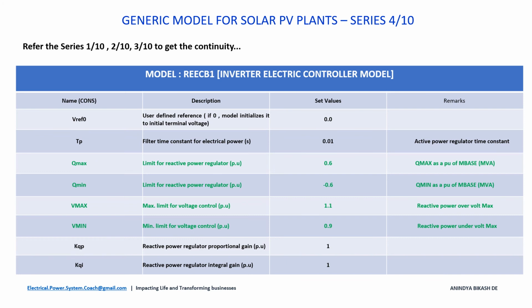Like in LVRT mode, it starts operating below 0.9. So 0.9 to 1.1, this is the continuous range you can say. And so below 0.9, it will go into LVRT mode, and above 1.1, it will go into HVRT mode. And there are various time instances, means from 1.1 to 1.2 it may withstand for certain seconds, then 1.2 to 1.3 it may withstand for certain lesser seconds. So likewise, this is the Vmax and Vmin. This is the nominal, and minimum and maximum value of the voltage during which the inverter will not respond to, in its ride through mode.